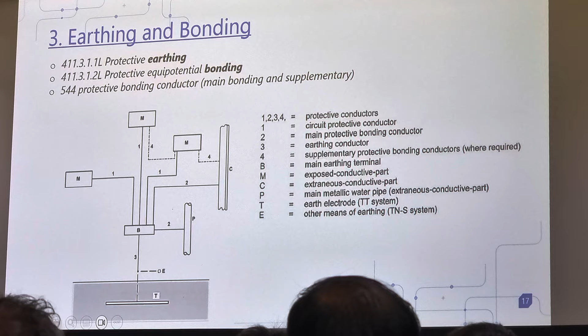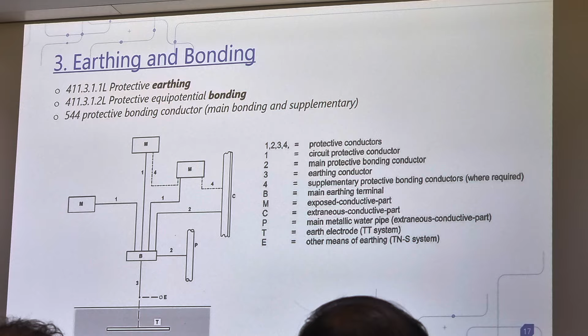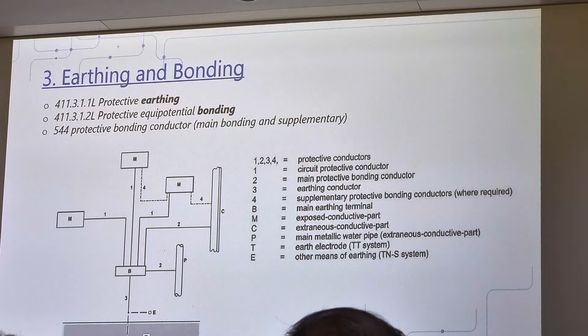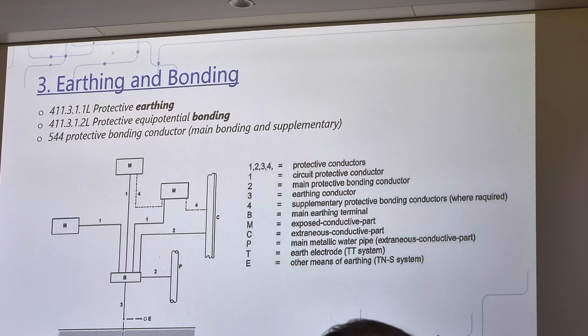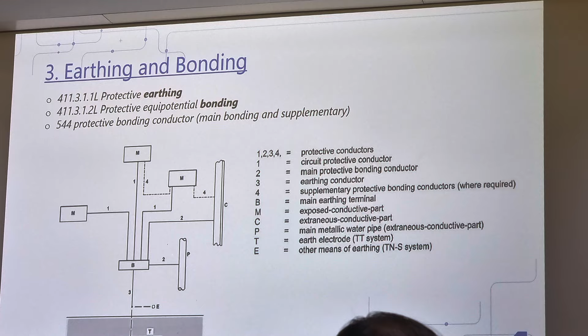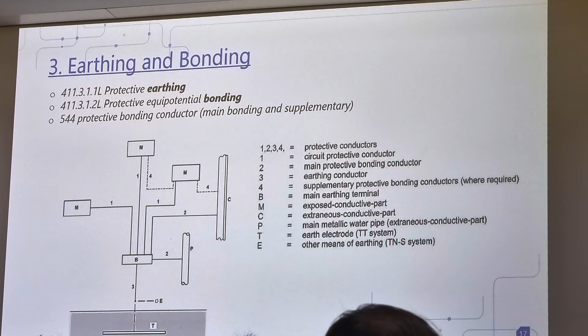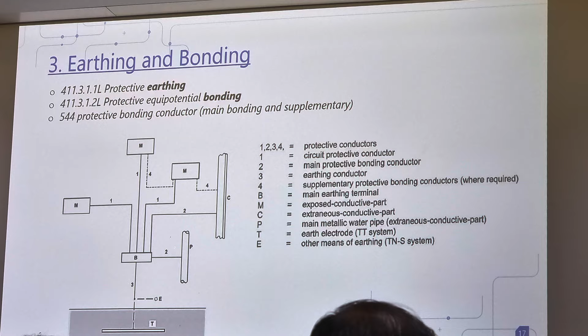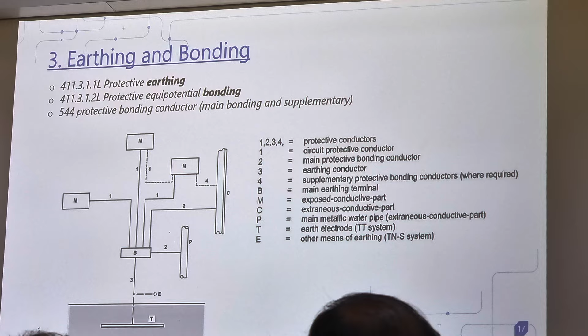under 628. So on top of that, under 544, we have one more, which is the protective bonding conductor for main bonding and supplementary bonding. So on top of bonding, which is the main bonding, there is also supplementary bonding. In situations where there are extra hazards, in situations where you need to make sure that the potential is as low as possible. So you have supplementary bonding. So supplementary bonding is not for all installations. There are specific installations where there are particular hazards where you need to put in supplementary. So if you do, then you look at 544. It talks about in what situation you need supplementary bonding and how to size the supplementary bonding. What is the size you need to use? On top of your main bonding, on top of your protective earthing, what size of cable you use in order to achieve this supplementary bonding.